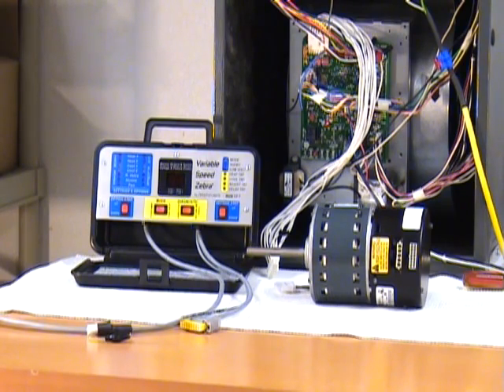Using the variable speed zebra dramatically reduces the likelihood of an incorrect diagnosis when a failure has occurred. But that's not all it does. Because the variable speed zebra reports system airflow in CFM, the tool is valuable when you're setting up a system for the first time. Balancing a system is much easier when you know the actual CFM a system is pumping at the blower. Many of these systems are dip switch adjustable up or down to meet a home's specific needs. The variable speed zebra reports those dip switch settings with tricolor LEDs to enable you to make better choices when you're first installing a system.